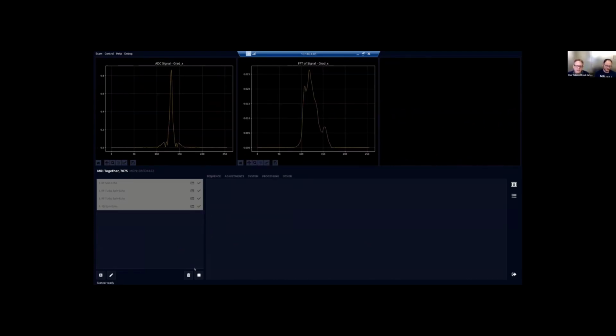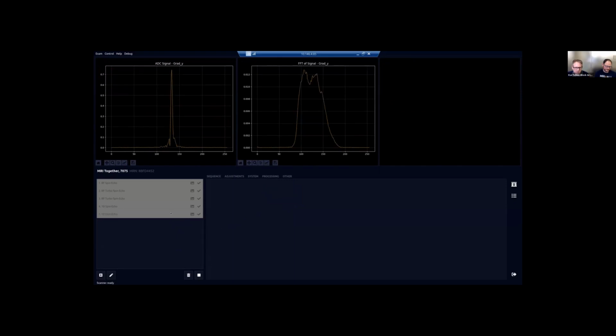And then the next step would be to run a spin echo sequence with a gradient enabled. So this would be the 1D spin echo sequence here. I can run this now. Gradient direction would be the X gradient. It's basically acquiring 1 spin echo with gradient encoding, so a projection. You can see the ADC signal here, and on the right side, the FFT of that. So a projection along the X direction of the scanner. I'm just going to quickly run this also in the other directions. This is now the Y direction, and let's run it in the Z direction.